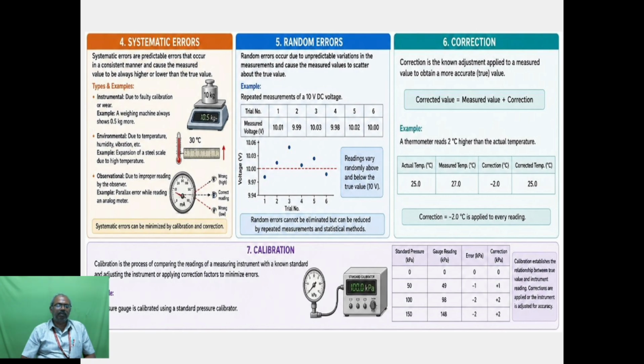The example for calibration is a pressure gauge calibrated using a standard pressure calibrator. This table shows the measurements during the calibration. Standard pressure is in kilopascal. Pressure is 0, gauge reading also 0, error is 0, there is no correction. If standard pressure is 50 kilopascal, the gauge reading shows 49. So the error is -1, so correction should be +1. Then next, standard pressure is 100, then gauge reading is 98. So error is -2, the correction is +2. Then standard pressure is 150 kilopascal, the gauge reading is 148. The error is -2, the correction is +2.